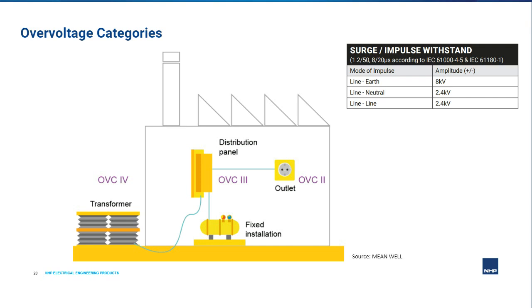The Cat 3 overvoltage category applies to components inside a distribution board or panel, for example fuses, isolating devices, circuit breakers, etc. The overvoltage transient levels seen by Cat 3 equipment are generally diminished in comparison to what is seen at the Cat 4 level.